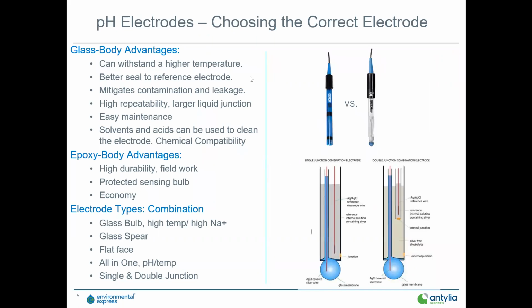Did want to do a quick review of the advantages. Obviously, the glass body electrode is going to withstand higher temperatures. It's going to have better chemical compatibility. Hydrofluoric acid, HF, is probably the only thing that's going to really attack that glass electrode with a ceramic junction. But it mitigates contamination and leakage, great repeatability, larger liquid junction on most, very easy maintenance. The key is that the glass body electrodes are normally a laboratory electrode. The majority of them are refillable to give extra value and a longer life to that electrode.